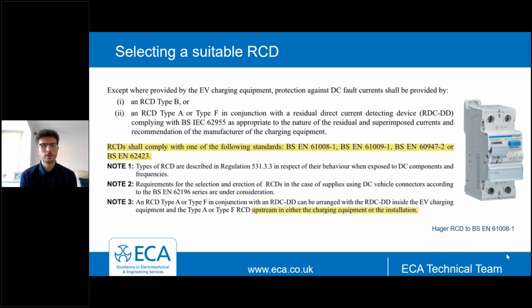But from our point of view, they're either compliant or they're not. So do they meet that standard? Can the manufacturer provide clarity that it meets BS EN 61008 as an example? From our perspective, the regulation here is quite clear that the RCD shall comply with one of the following standards. So if you're looking to achieve compliance here, you should confirm that the device meets one of those standards.